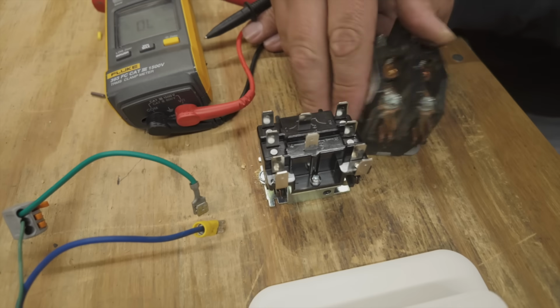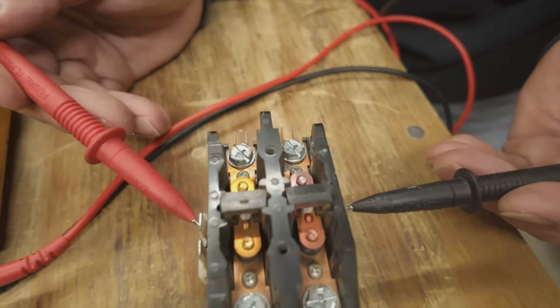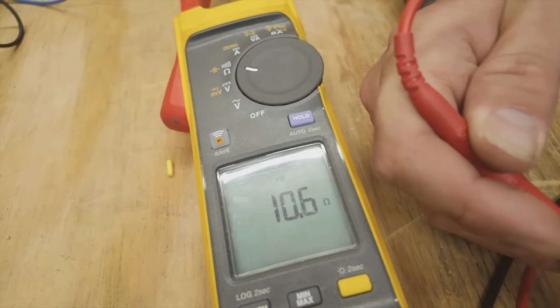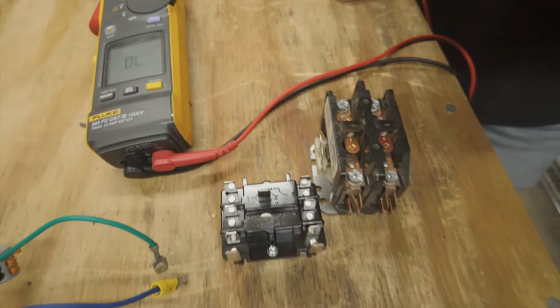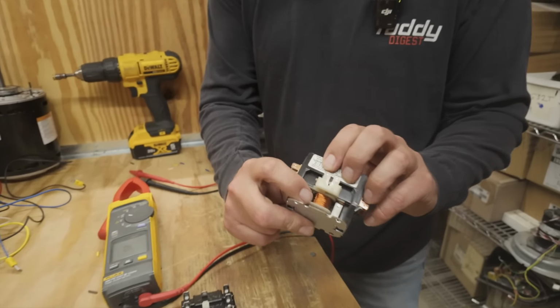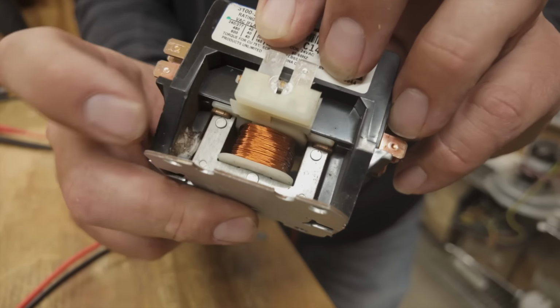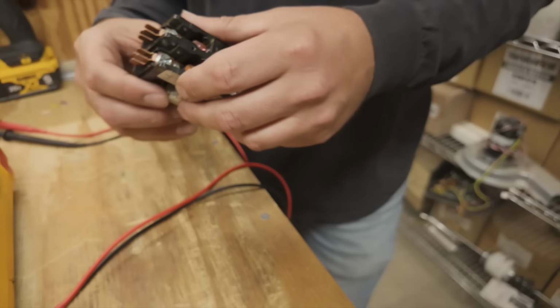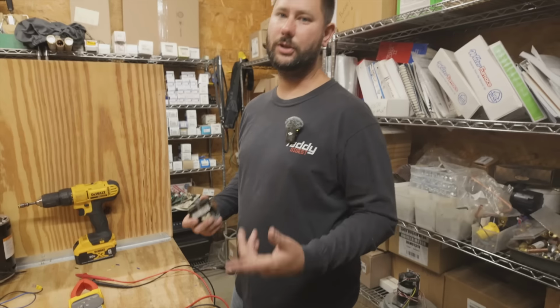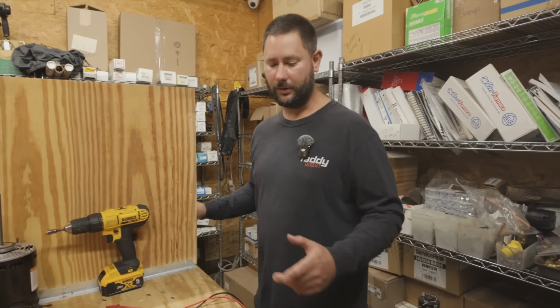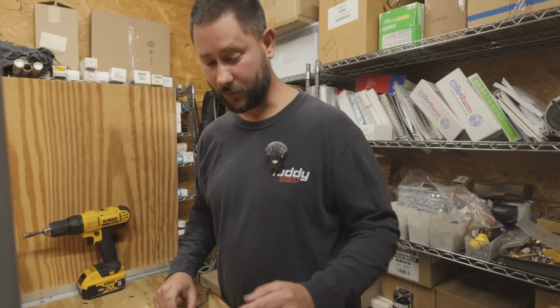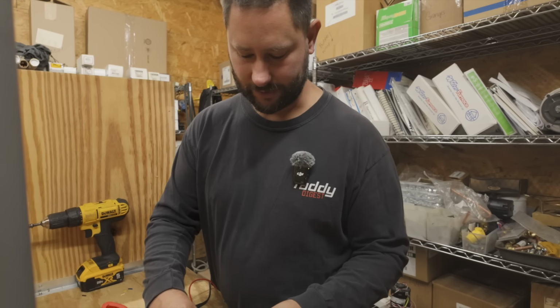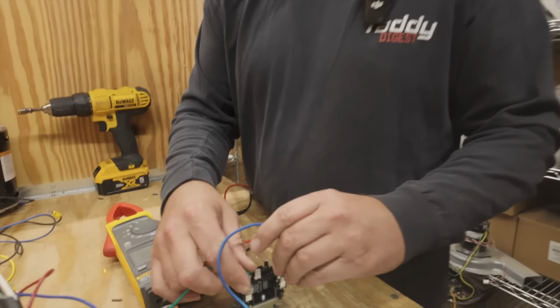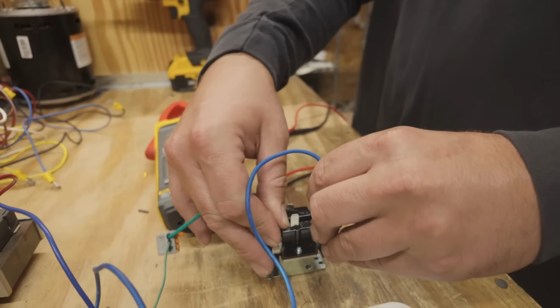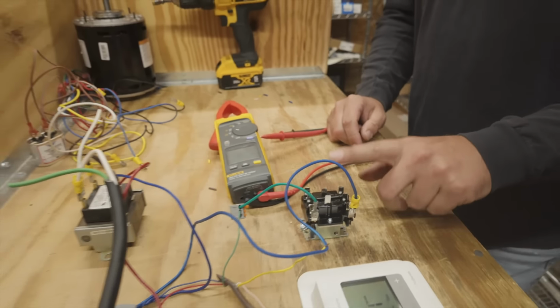Contactor is the same. Watch. Checking the coil of the contactor. 10. That's a good reading. Now, if you have a burnt coil, you're going to see it. It's going to be black. Typically a short will cause that. And then the reading is going to be off. It's going to be like 1 or 2 or 0, something crazy like that. Just want you to know that. But you can see we have a good coil. You can tell because of the nice copper. It's not burnt.